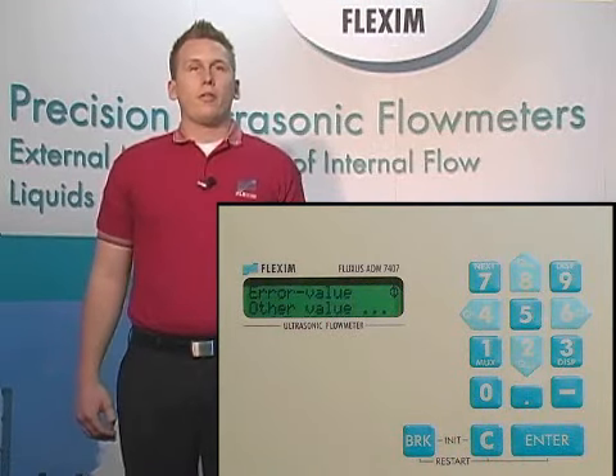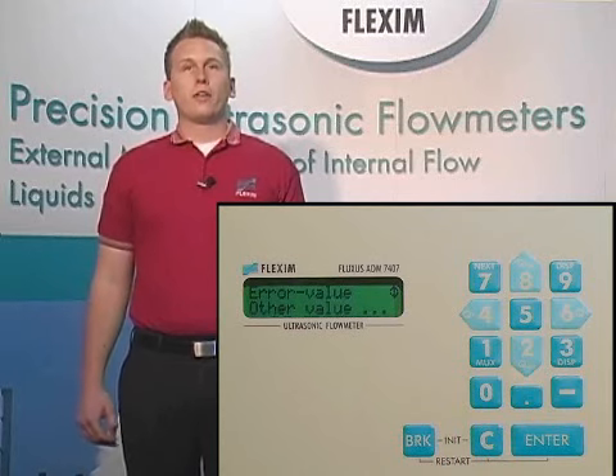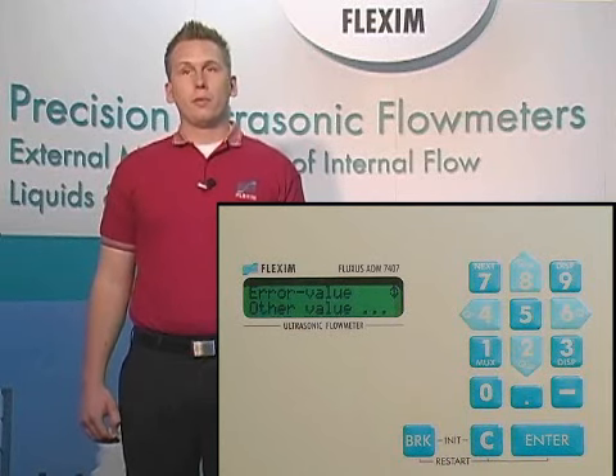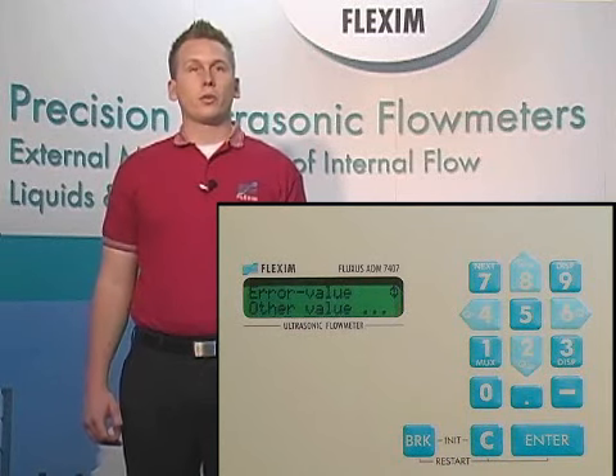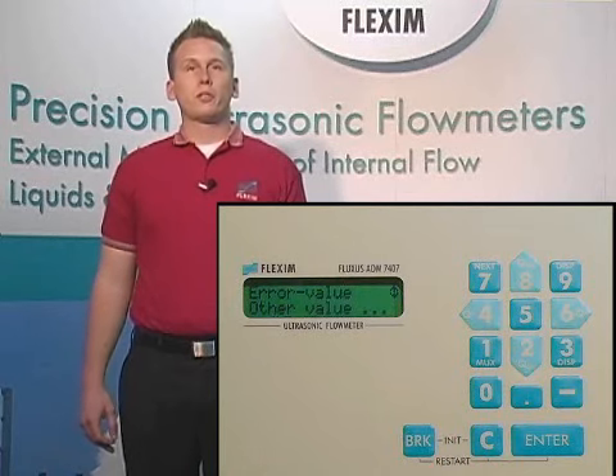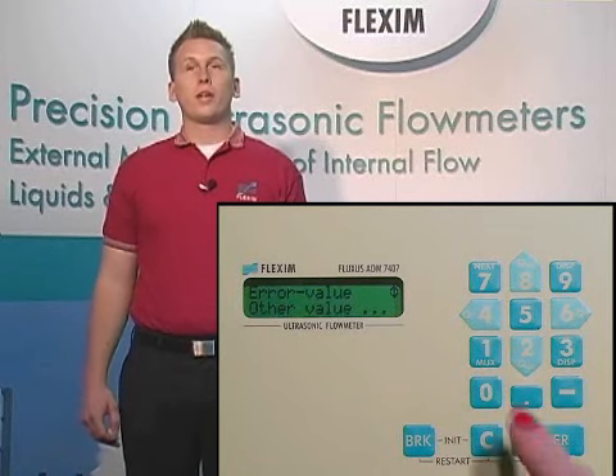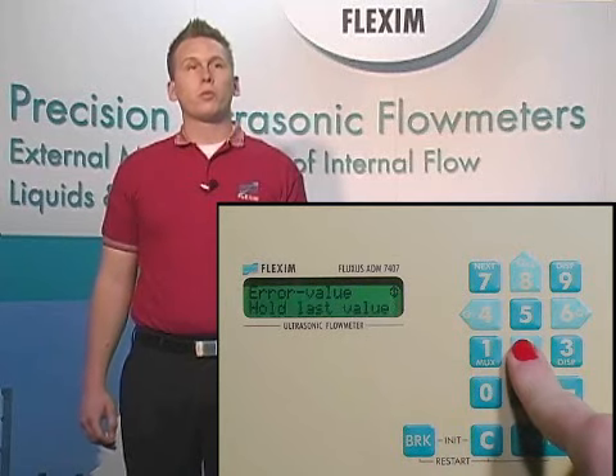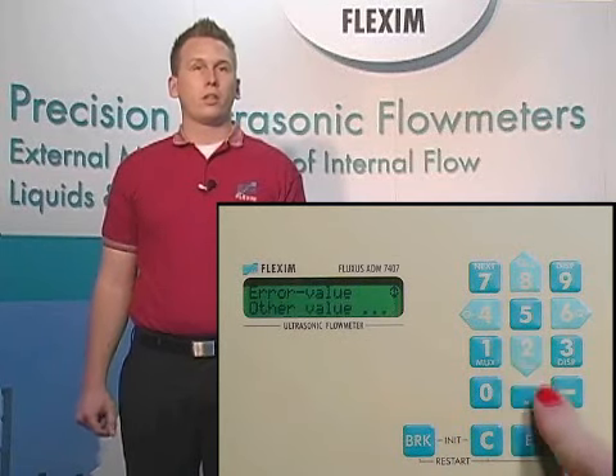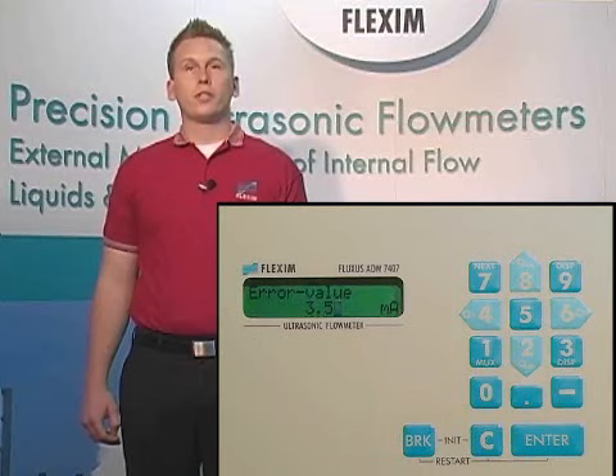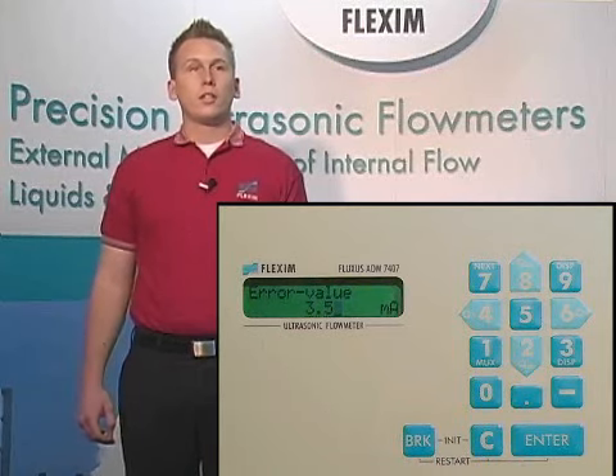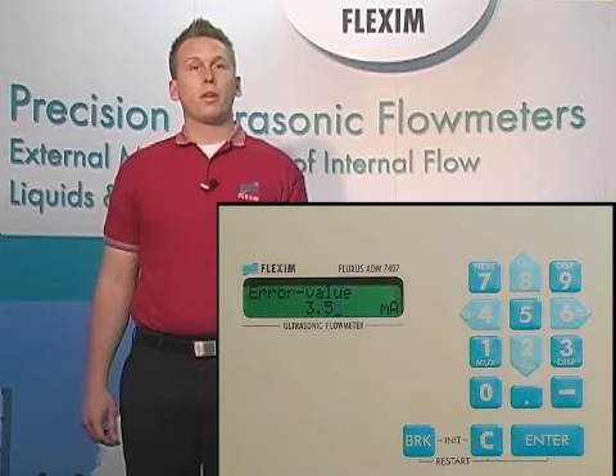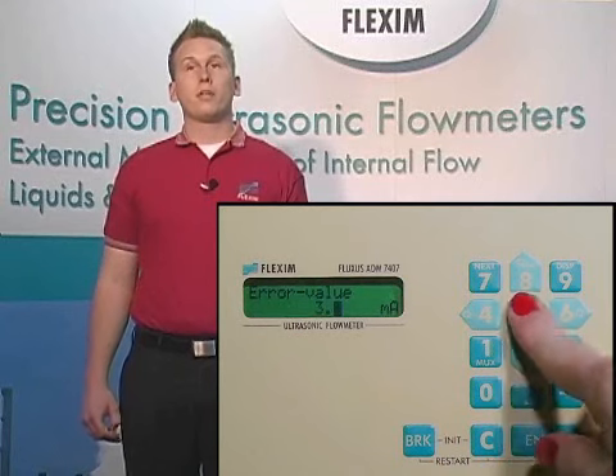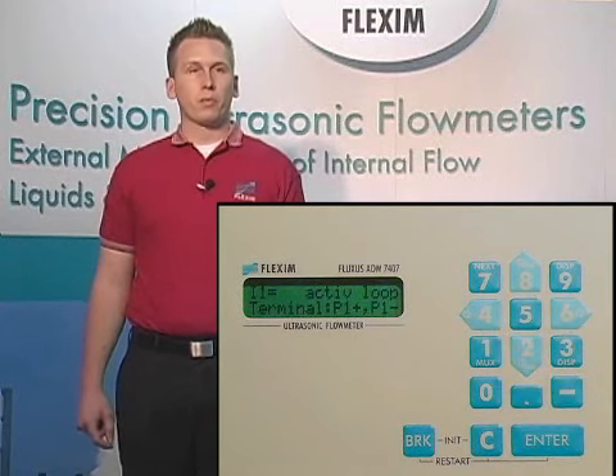This brings us to the error value option. This is the value that you'll see from the meter if the pipe becomes empty or we get lots of entrained gas or solids. We can choose from holding the last value until we're able to read again, 0, 4, or 20 milliamp, or some other value. We found that the best choice here is to generally use other value and select 3.5 milliamps. This way, if you ever see 3.5 milliamps on the PLC, you know that your pipe isn't full or that you have something undesirable happening in your pipe.